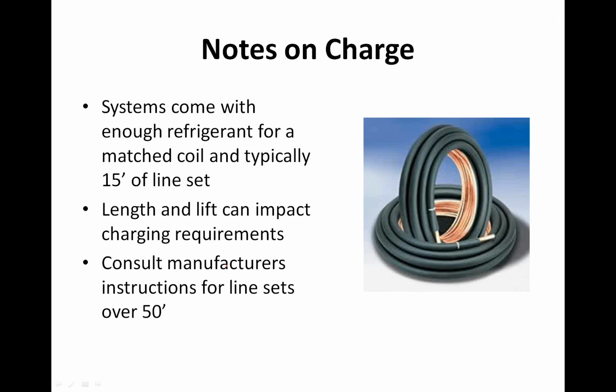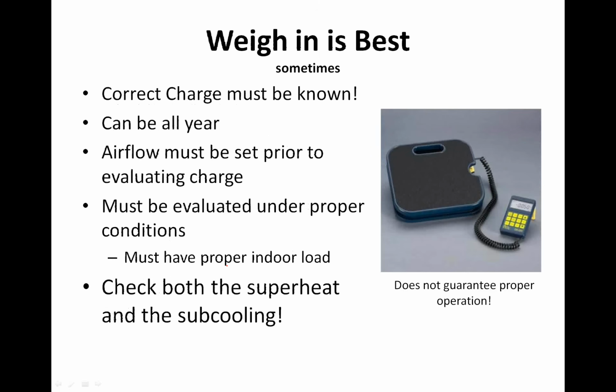Things like length and lift will impact the charge requirements, so you've got to make sure those are taken into consideration. If we're talking excessively long line sets, over 50 feet, you've got to consult the manufacturer's requirements, because it may even require you to change line sizes to accommodate the pressure drop in that liquid line. You may have to go up a line size when you get into longer line sets.